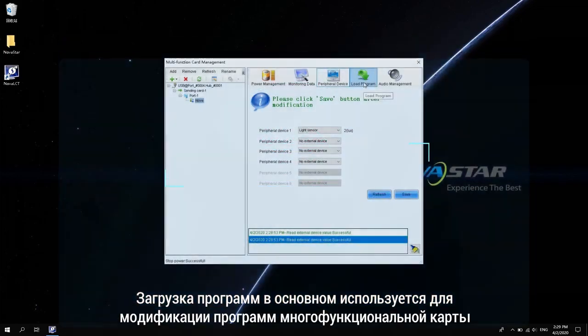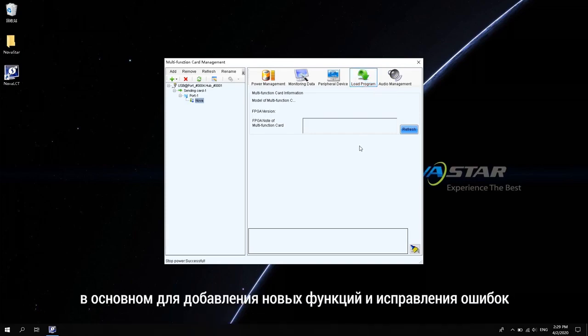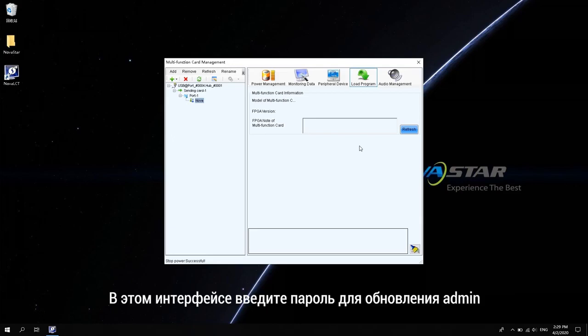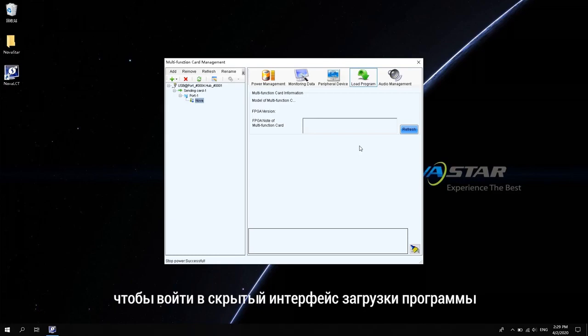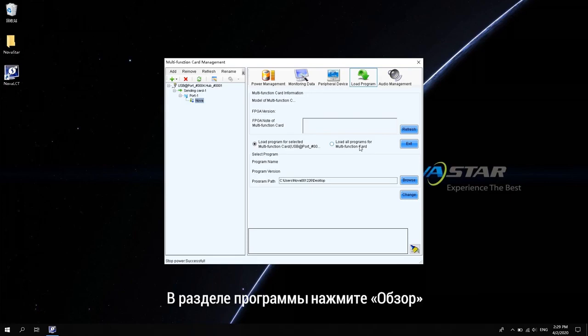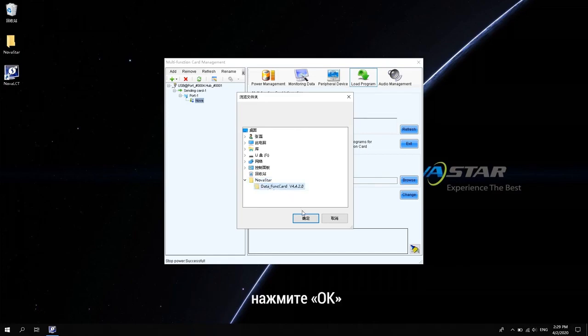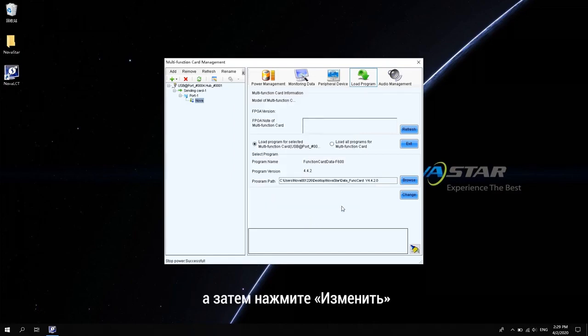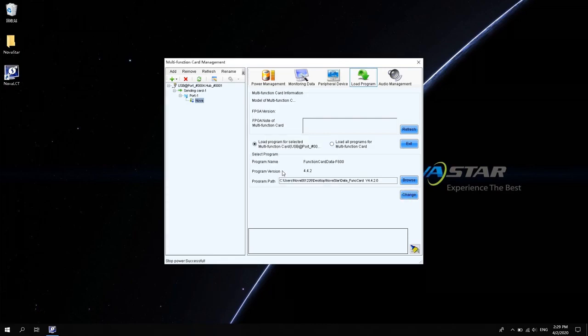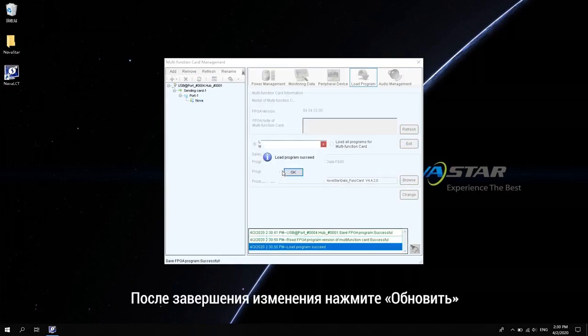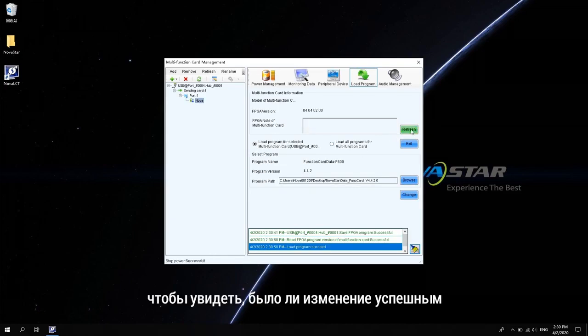Program loading is mainly used to modify the programs of the multi-function card. Mainly to add new functions and fix bugs. On this interface, enter Update Password Admin to let the hidden program upload interface show. In the program path, click Browse to select Downloaded Program. Click OK and then click Change. After the change is complete, click Refresh to see if the change is successful.